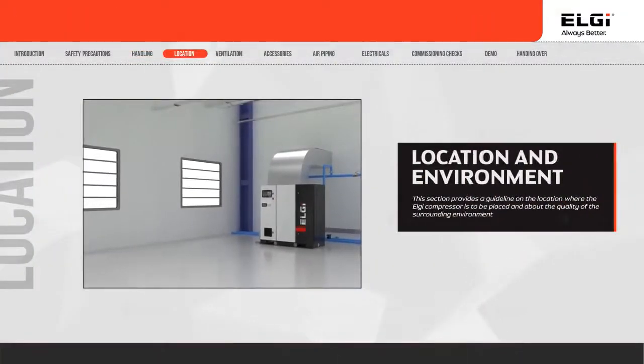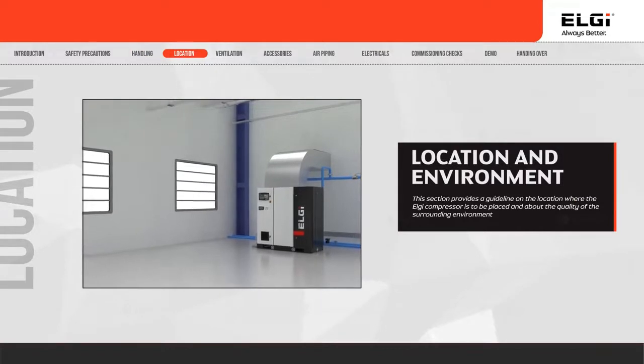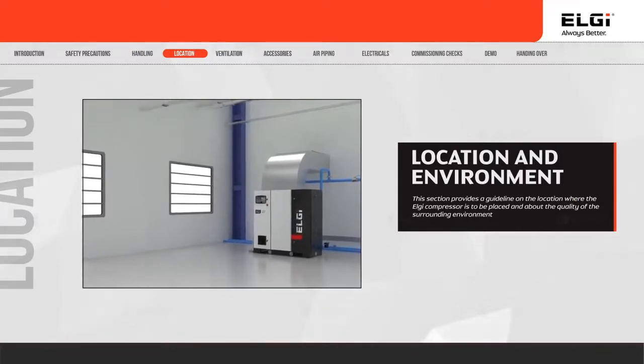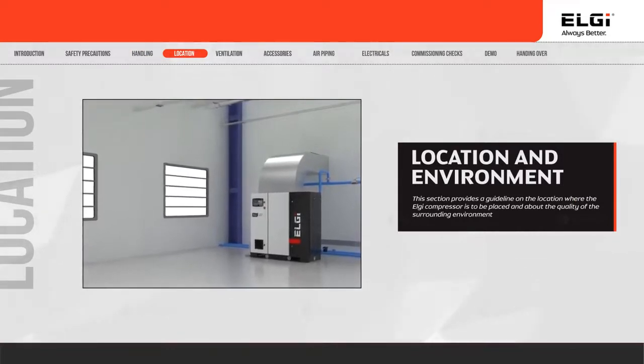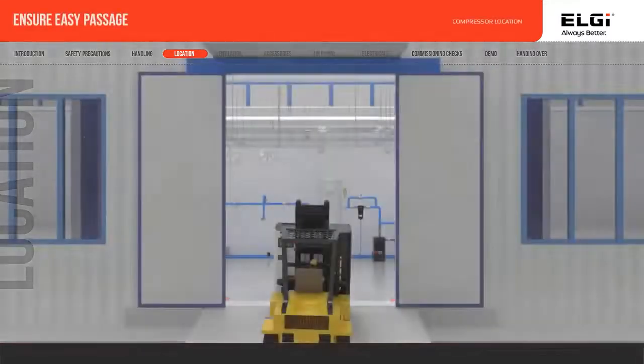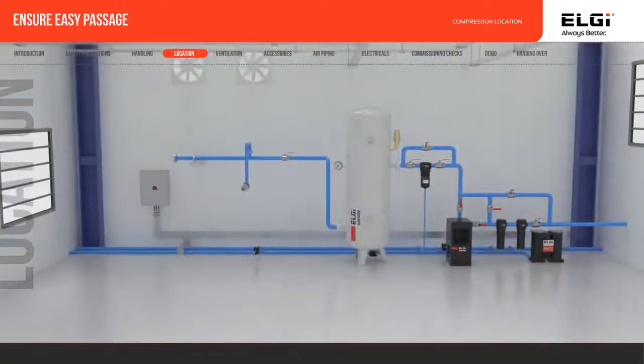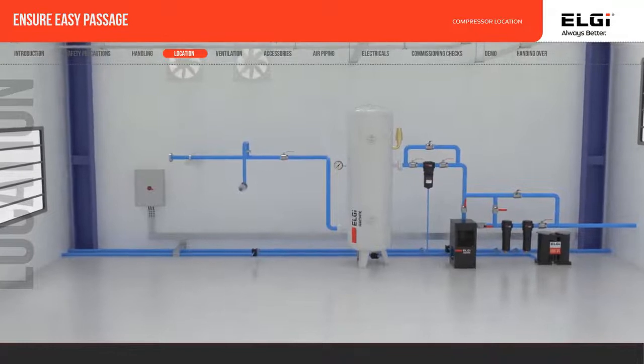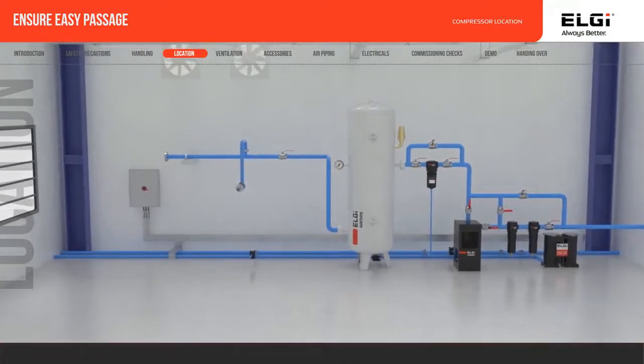The location and environment where the compressor is to be installed impacts the performance. A compressor should never be installed in the open. Hence it is important to follow the guidelines specified in this section. Ensure the compressor room entrance has sufficient space for compressor passage. Also make sure that the air compressor is installed in a clean and dust-free room.